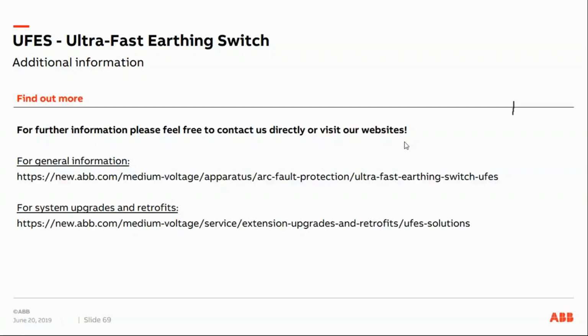There's another question: what would the use of the UFES reduce the cal per square centimeter to? Well, as mentioned before, I think you're referring to the example which I've just been talking about with the current limiting fuse. In this example, it was tested that the energy level peak was half a cal per square centimeter.